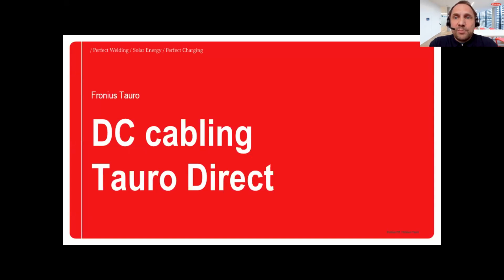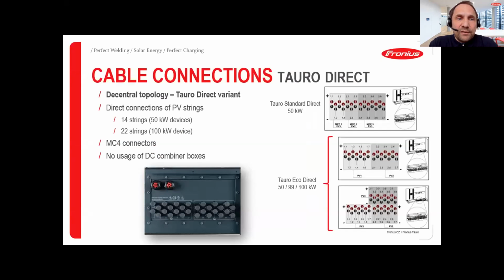As we talked about AC cabling at the beginning, now we have the DC cabling, starting with the Tauro Direct. This is the bottom of the inverter where you can see how many strings you can connect directly. We use MC4 connectors, and for the 50 kilowatt device there are 14 strings available, while for the 100 kilowatt device there are 22 strings available.